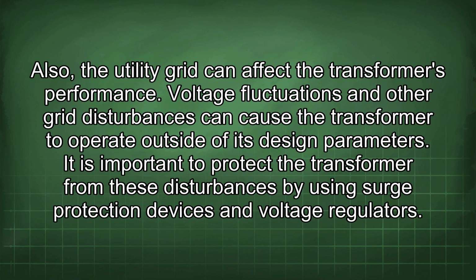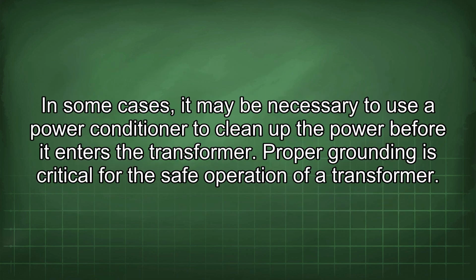Also, the utility grid can affect the transformer's performance. Voltage fluctuations and other grid disturbances can cause the transformer to operate outside of its design parameters. It is important to protect the transformer from these disturbances by using surge protection devices and voltage regulators. In some cases, it may be necessary to use a power conditioner to clean out the power before it enters the transformer. Proper grounding is critical for the safe operation of a transformer.